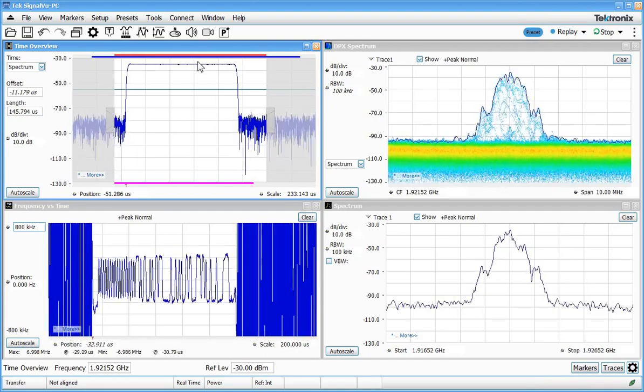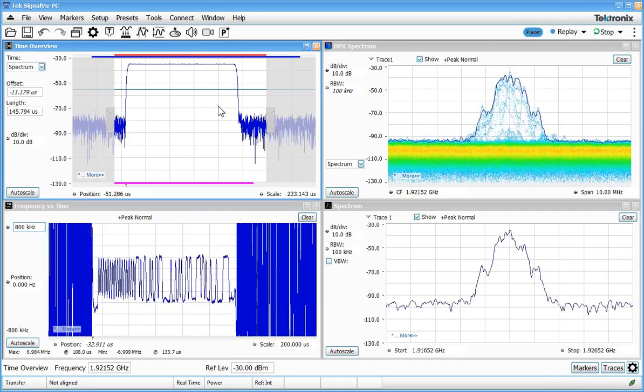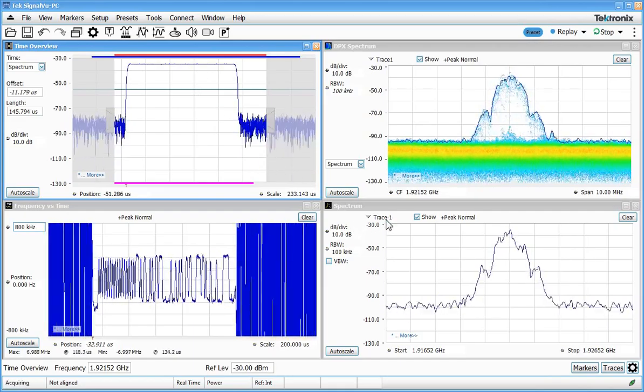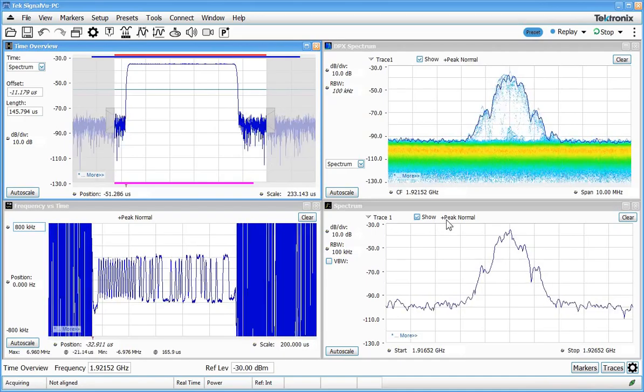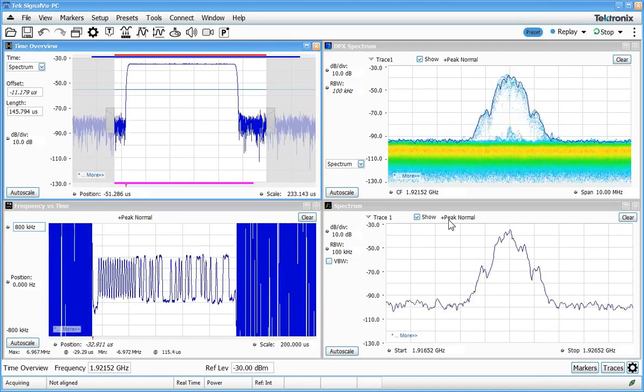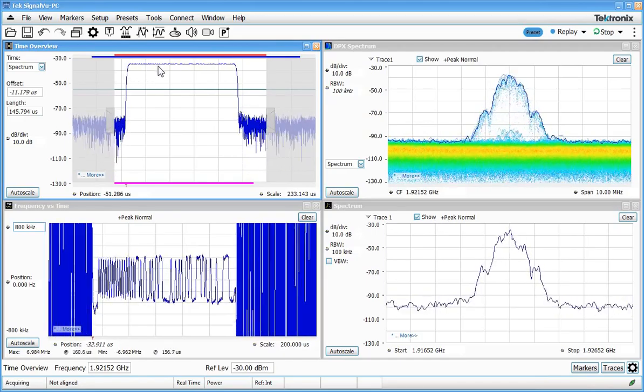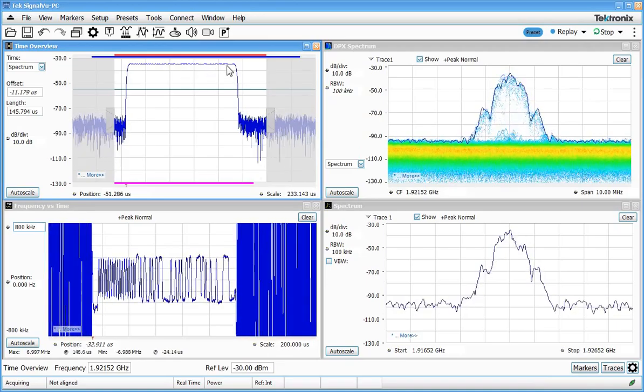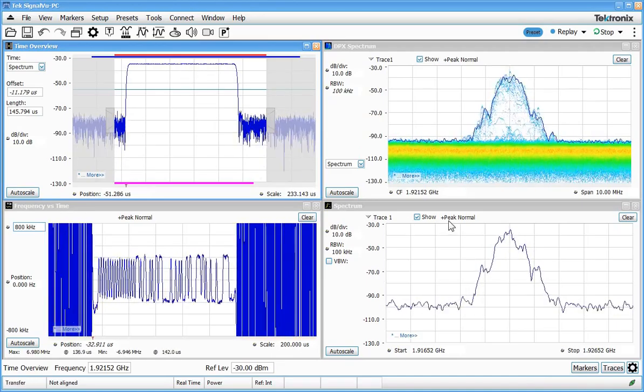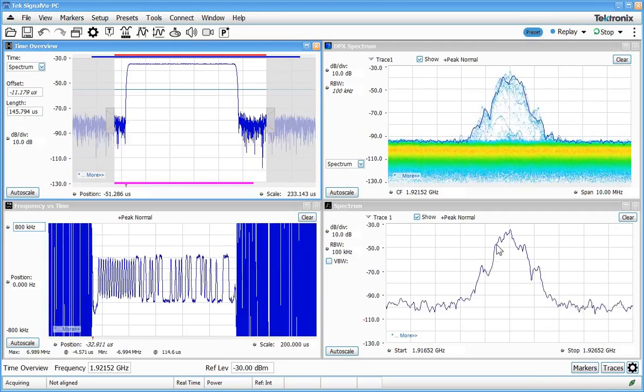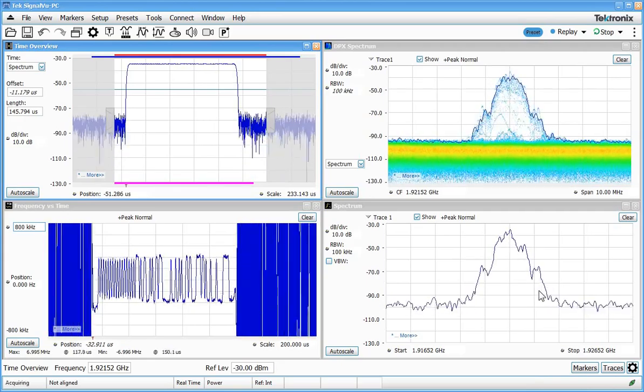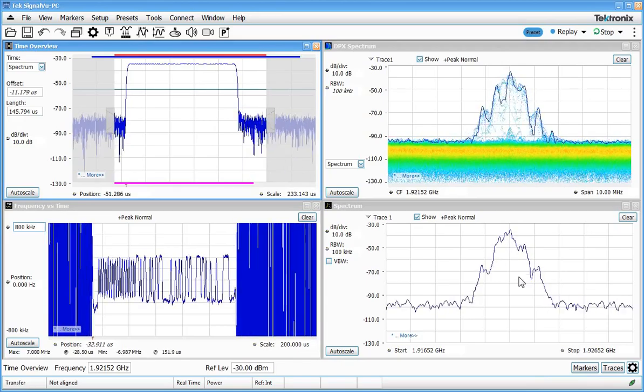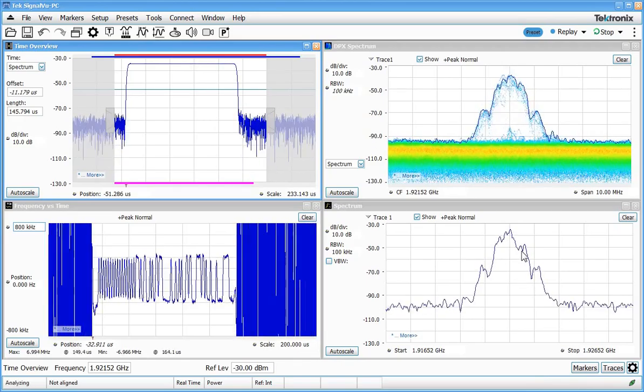So what it will do is compute multiple discrete Fourier transforms and give me a number of spectrum results. And what it does then is pass each of those spectrum trace results through whatever trace detector we have selected. In this case we have a positive peak trace detector. So we're going to take those multiple spectrums that were computed across this acquisition, pass each of them through that positive peak detect, and this shows me now the positive peak detect result of those multiple spectrum traces that were computed across that acquisition.